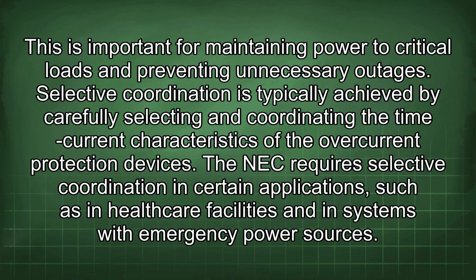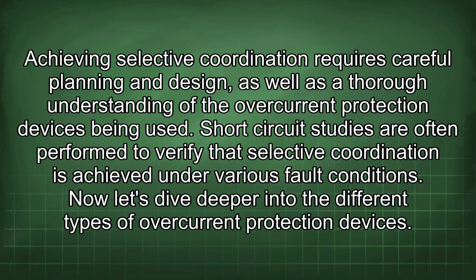Selective coordination is typically achieved by carefully selecting and coordinating the time current characteristics of the overcurrent protection devices. The NEC requires selective coordination in certain applications, such as in healthcare facilities and in systems with emergency power sources. Achieving selective coordination requires careful planning and design, as well as a thorough understanding of the overcurrent protection devices being used. Short-circuit studies are often performed to verify that selective coordination is achieved under various fault conditions.